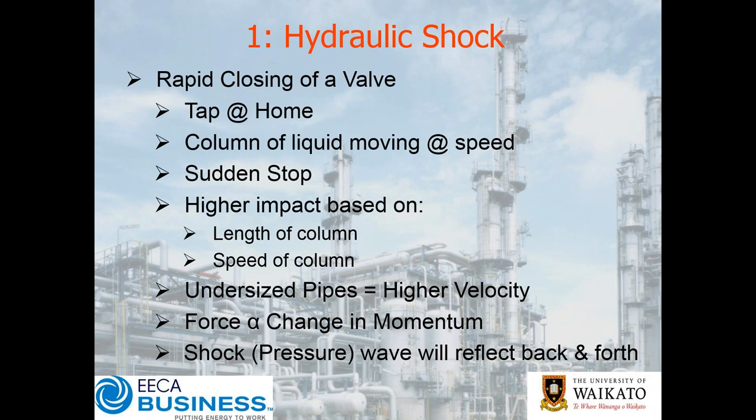If we have a small-diameter pipe, the velocity is going to be quite high. If it's quite a long pipe back to where the water's coming from, we have a long column. So number one: undersized pipes give you high velocity, and high velocity is going to give you a problem. The best way to look at this is: force is directly proportional to the change in momentum. The shock or pressure wave is going to bounce around, so it's not just a single bang — it could result in multiple bangs.